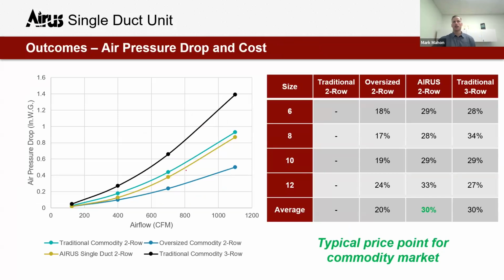We're going to continue here with a couple more product considerations from a performance perspective. From a cost perspective, I do want to note, the target here for us is to have this as a commodity product at a commodity price point. We envision this being used in lieu of 3-row coils in a lot of considerations and times. So this is priced on average, identically to a traditional 3-row coil and box. So no, we're not doubling the price of the single duct unit. That is not the intent.